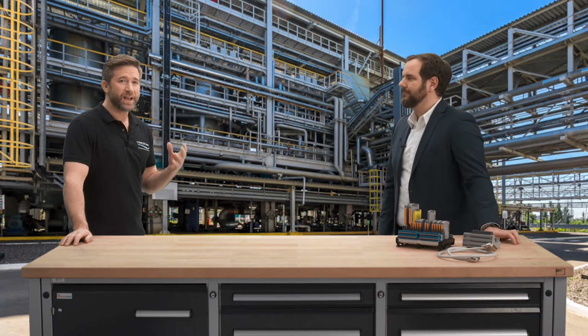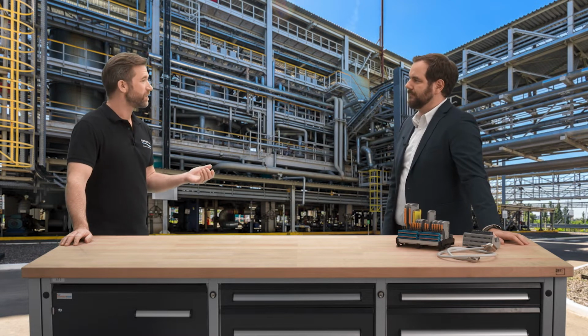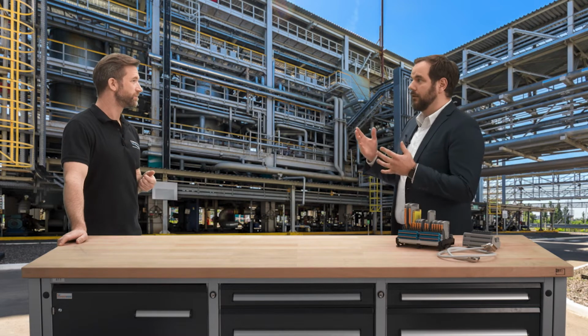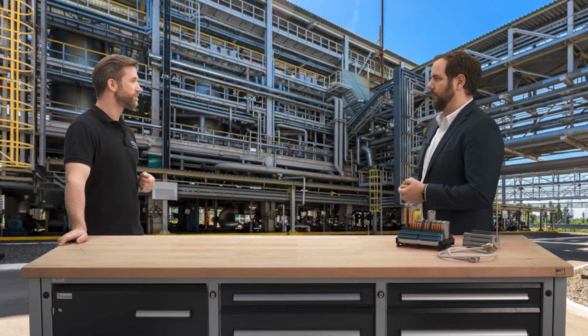So does universal I/O meet all customer requirements then? Universal I/O systems are great, but they truly have some limitations. For instance, everything is based on a 24-volt DC system. So if we have requirements above 24 volts, like 120 or 230 volts, this cannot be solved by the universal I/O system itself. Same counts for the current. There is a current limitation in the system.